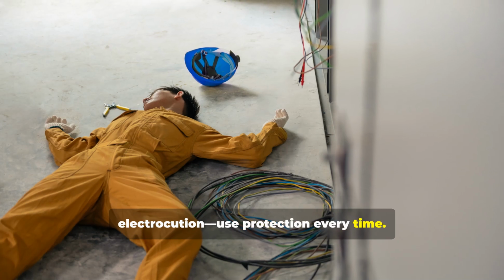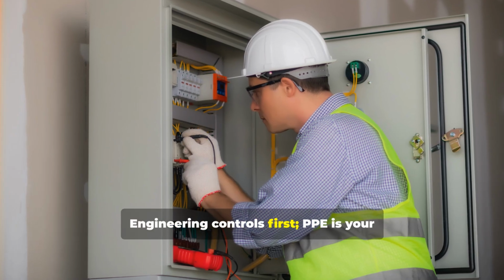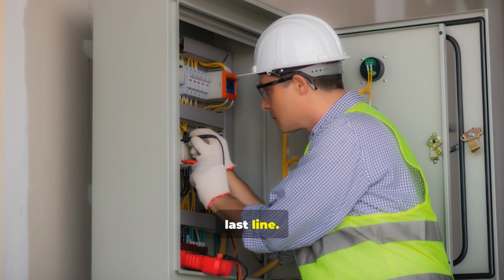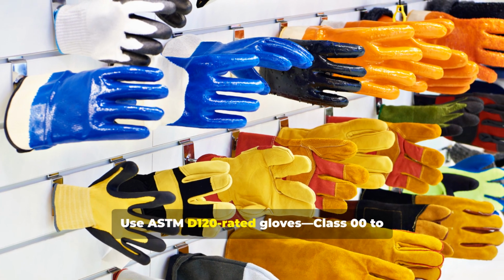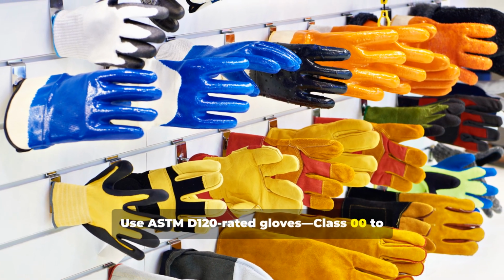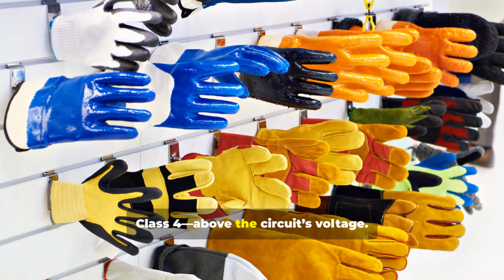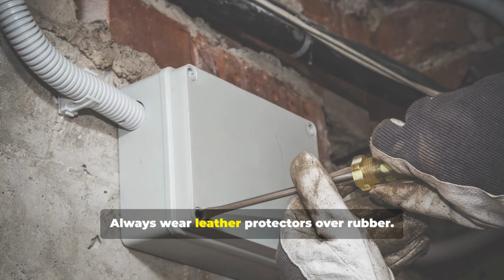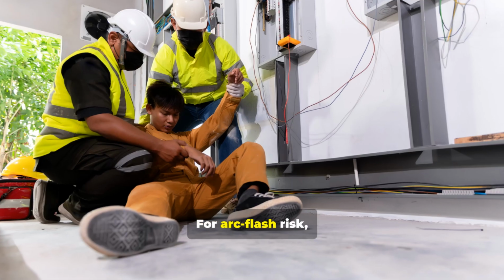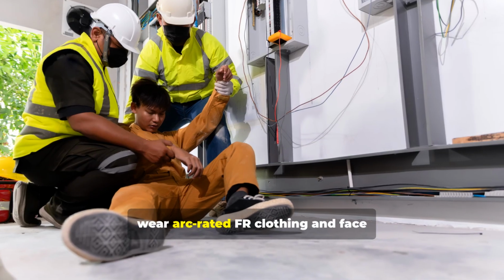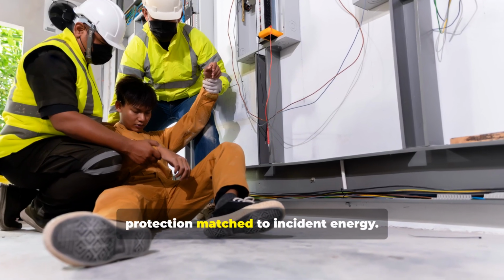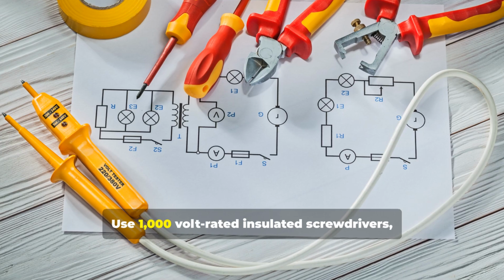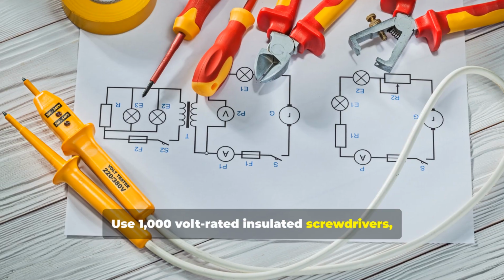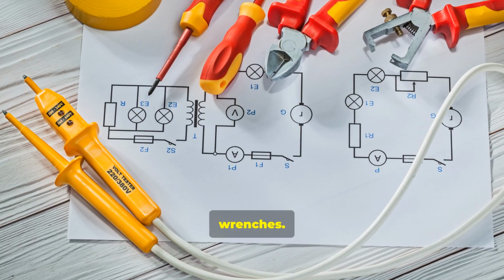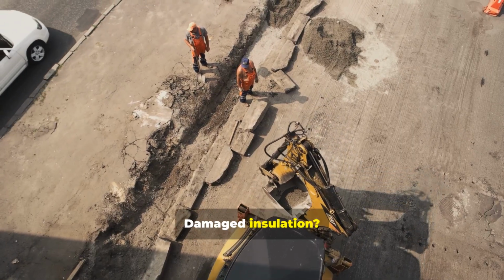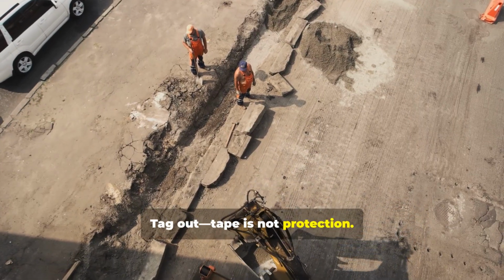Use protection every time. Engineering controls first. PPE is your last line. Use ASTM D120 rated gloves, class 00 to class 4, above the circuit's voltage. Always wear leather protectors over rubber. For arc flash risk, wear arc-rated FR clothing and face protection matched to incident energy. Use 1,000-volt rated insulated screwdrivers, pliers, wrenches. Damaged insulation? Tag out. Tape is not protection.